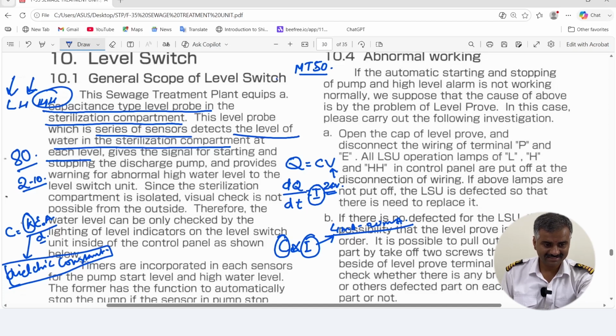So as the dielectric changes, your capacitance level probe, which is lying over here, has sensors. Say at this level, the low level, there is no water at this moment, and there is a water level here. So there is air over here. If there is no water, air has a different dielectric, due to which a different current is flowing through the circuit at this moment. As soon as the level increases to this level, water comes in here.